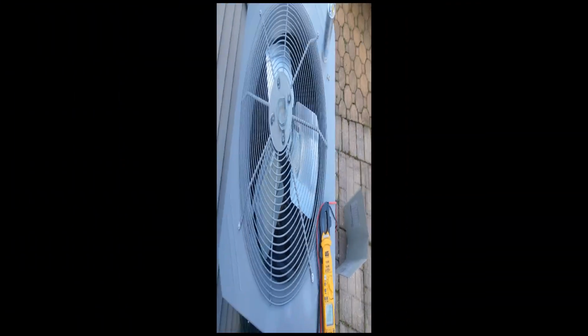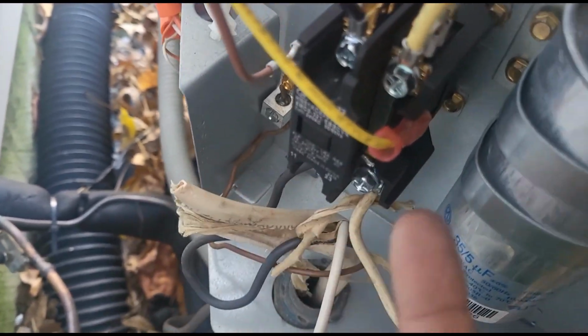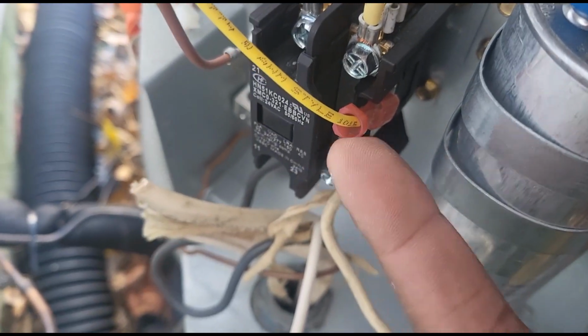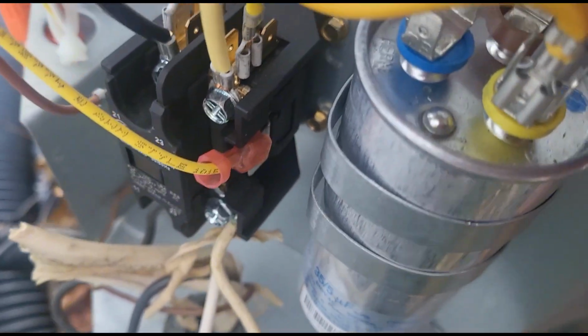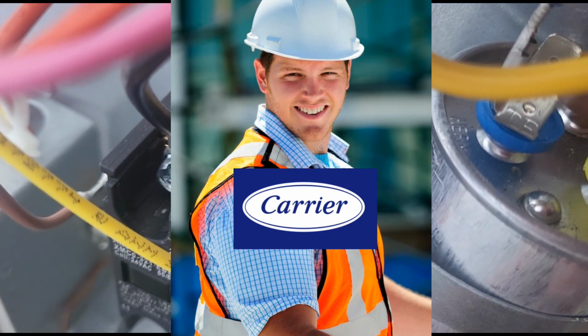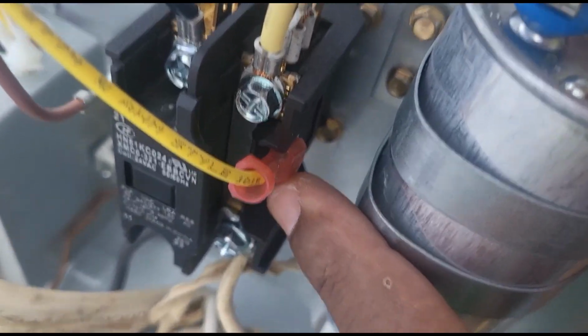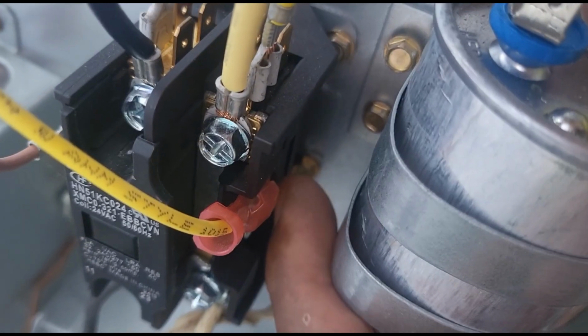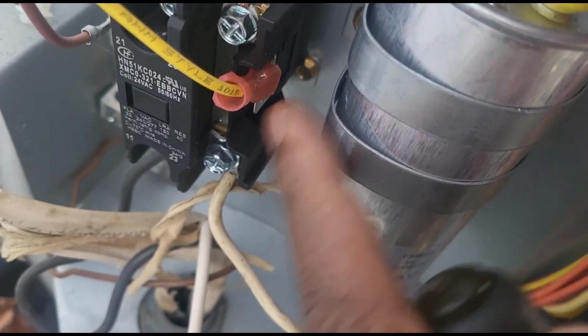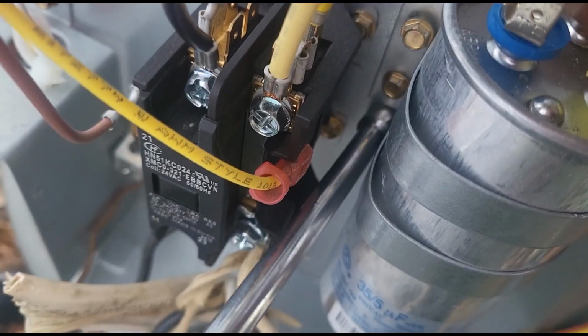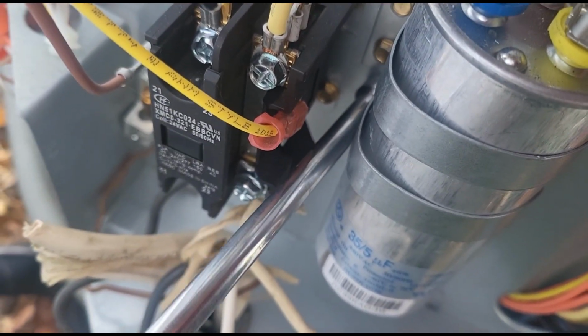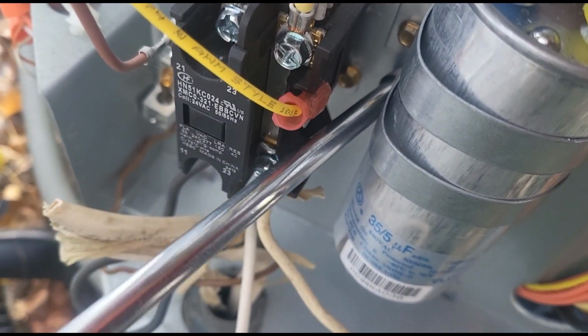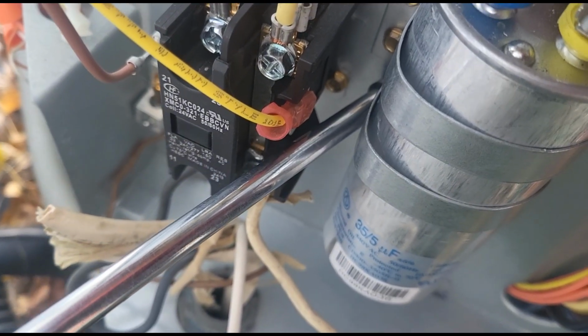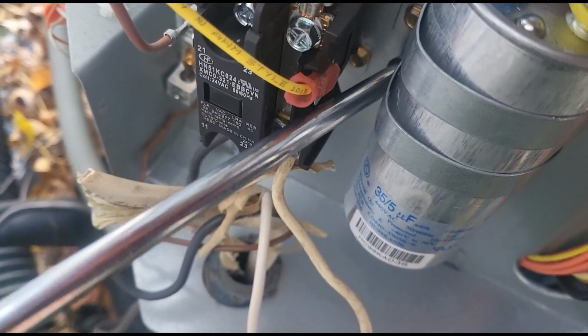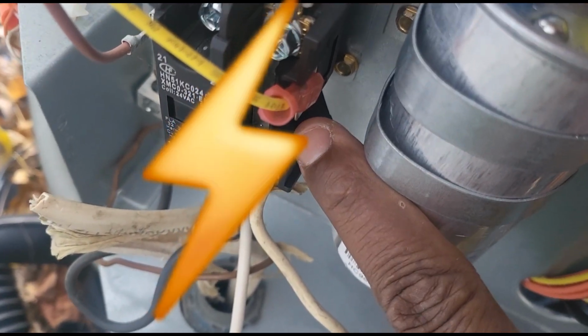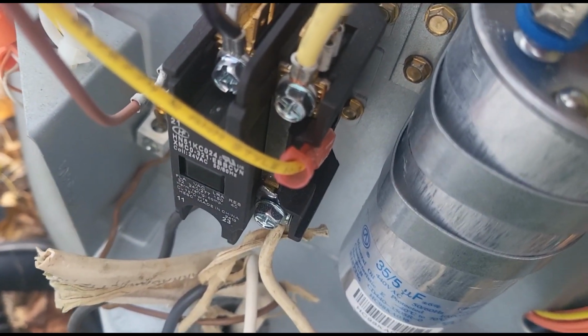I'll be right back. And if you know, you know, there's a reason why the 24-volt terminal closest to the capacitor is insulated. Reason being, guys, with ICP, meaning Carrier, Bryant, Payne, with their heat pumps, they like to put the capacitor screws within inches of your contactor coil. And guys, right now I got the power off inside, but if this thing was running, and if this was 4 o'clock on a Friday and I'm trying to get in and out, if I'm not careful and I unscrew the capacitor and I put my nut driver too close to the contactor coil, instantly this will either kill my transformer or kill my fuse inside.